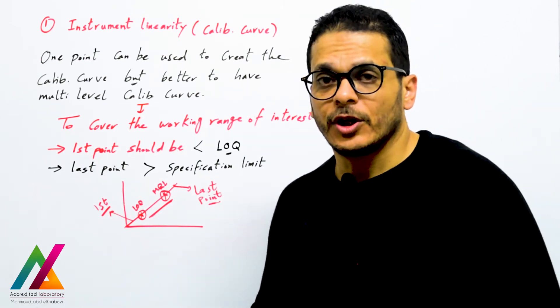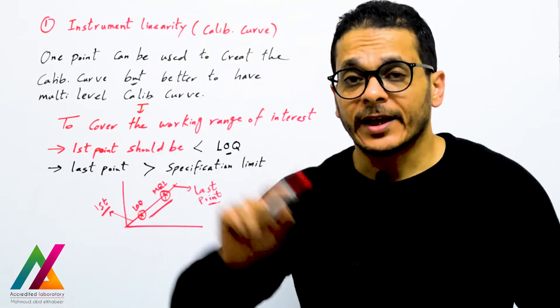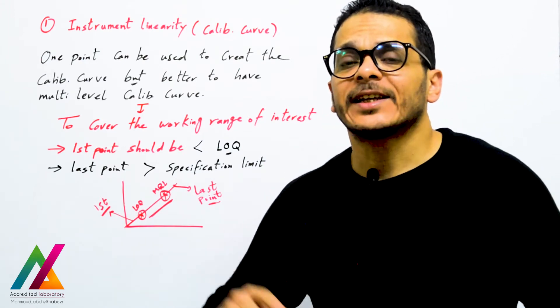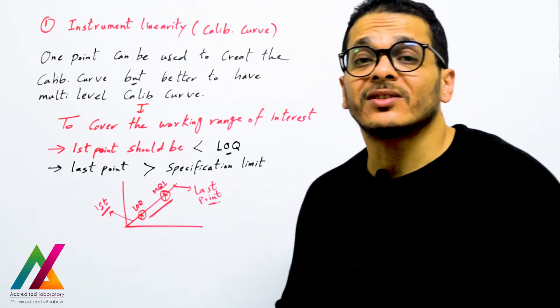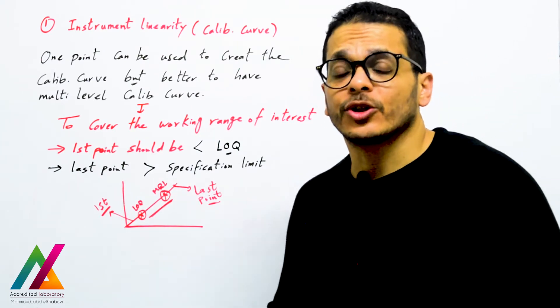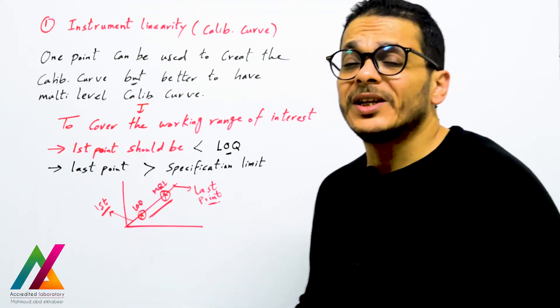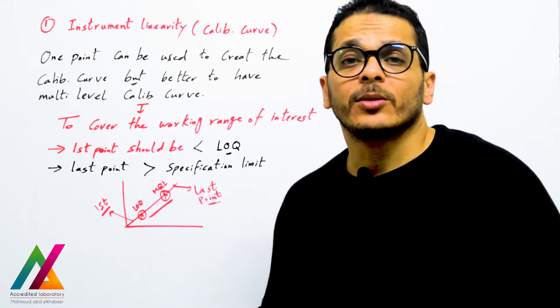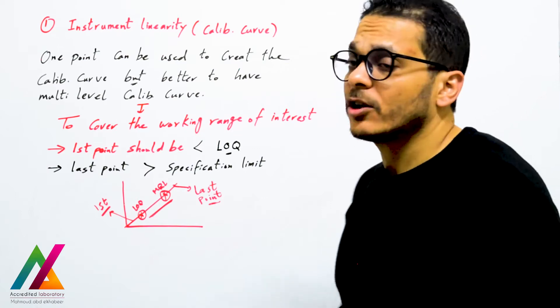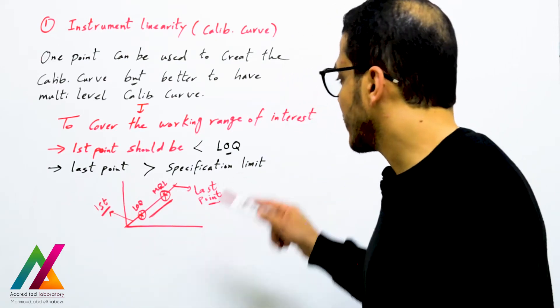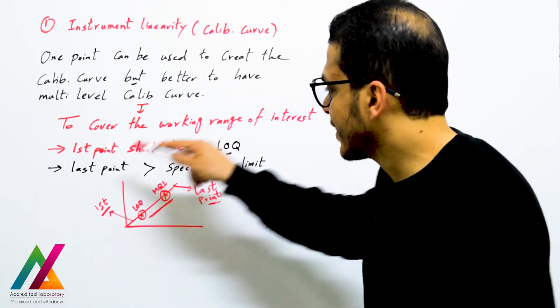One point can be enough to create the calibration curve, but it is better to have a multi-level calibration curve. You run different calibration standards to get different points covering the working range of interest — the range of concentrations expected to be measured by the method. The first point should be lower than the minimum reporting limit or limit of quantitation, and the last point should be higher than the specification limit or maximum residue limit.